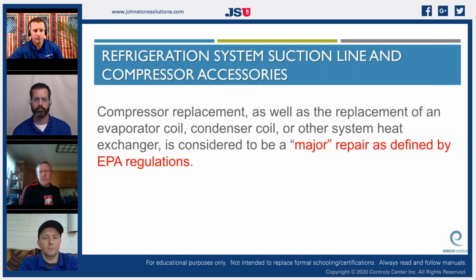Very important here: the four components that the EPA defines as a major repair are compressor replacement, evaporator coil, condenser coil, or auxiliary heat exchanger. That's how it's worded. Those are major repairs. If you have to remove or replace one of those things, or even repair them, it's considered a major repair.